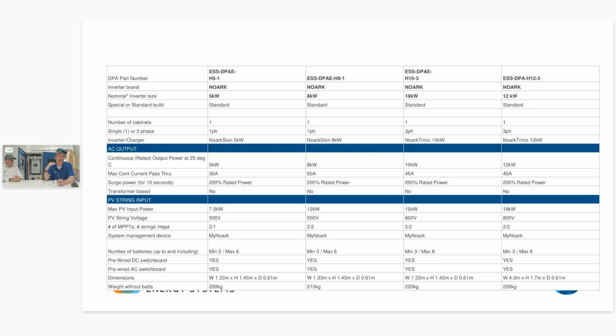So typically you can charge and discharge a managed battery more than an unmanaged one, and it broadcasts its voltage to the system, which stops charging when it hits that. If it doesn't change that value, that's just the end of the absorption cycle, and then it goes to float. When setting these up in a Victron system, you'd still put all the charge parameters into the MPPT and inverter as hard-coded values, just as a fallback in case it loses comms. But while it's under managed control, it's just being told what to do by the BMS.